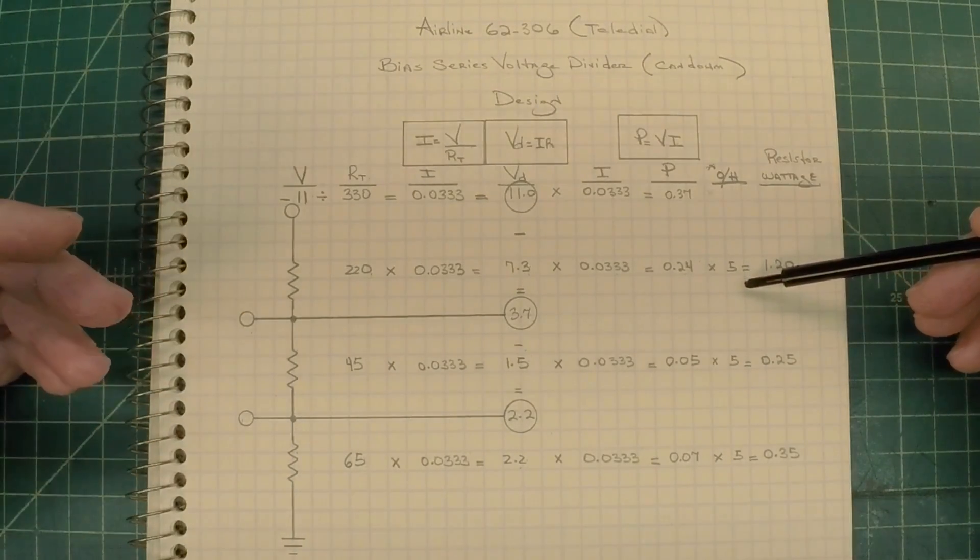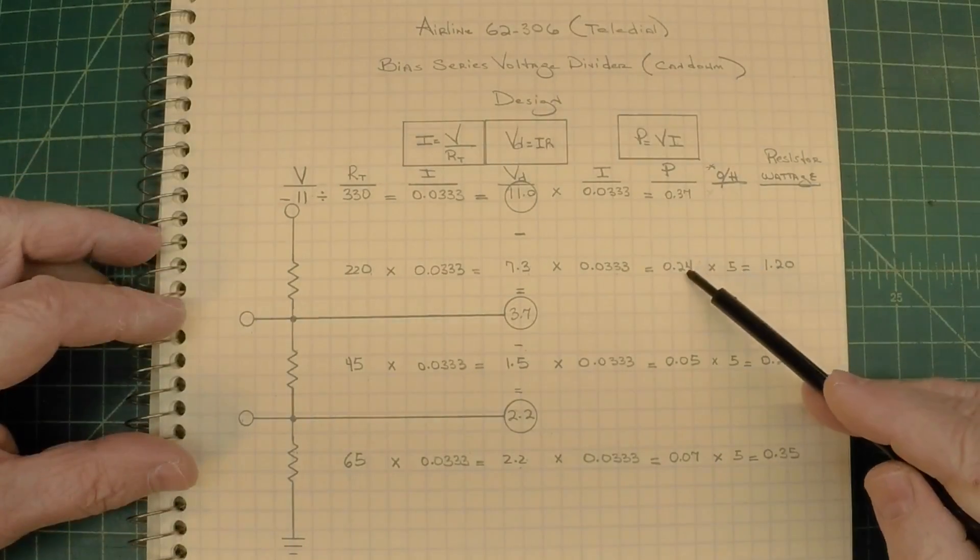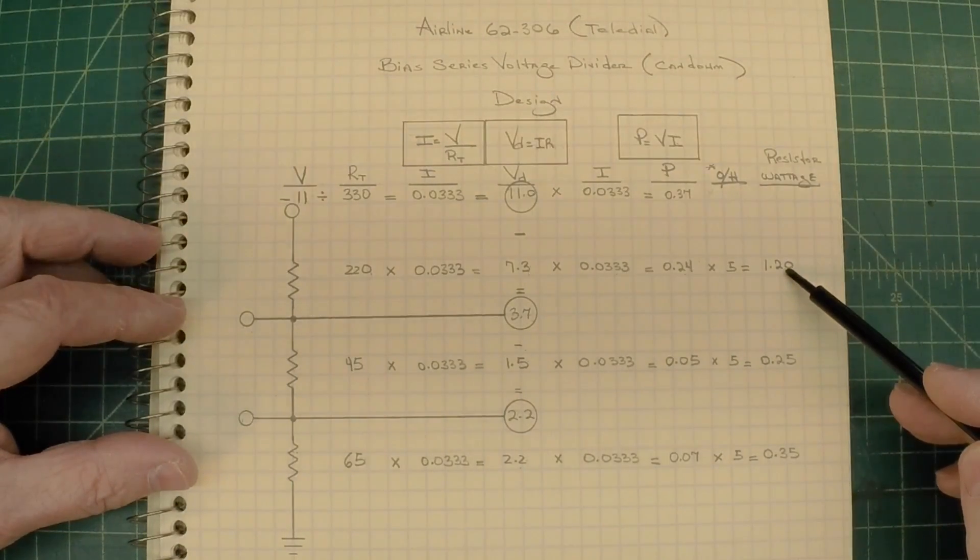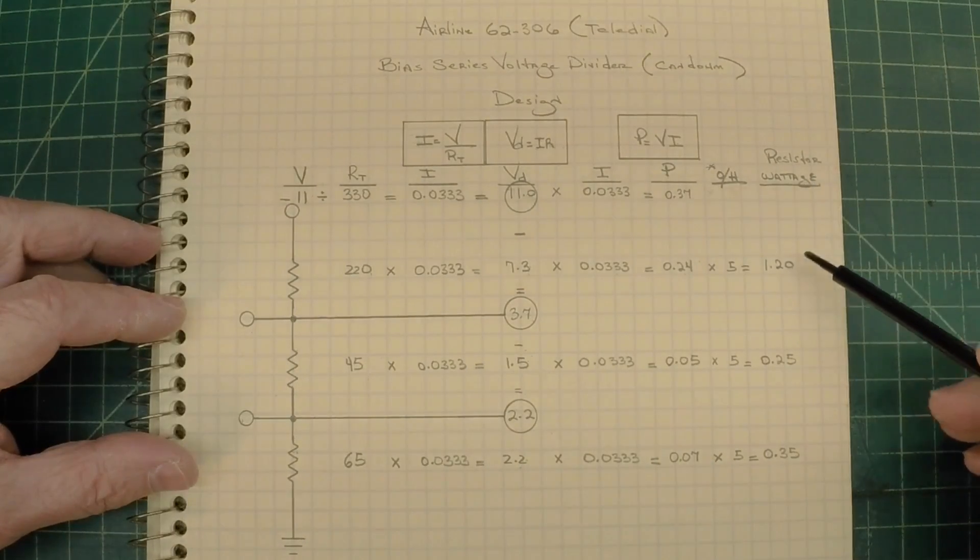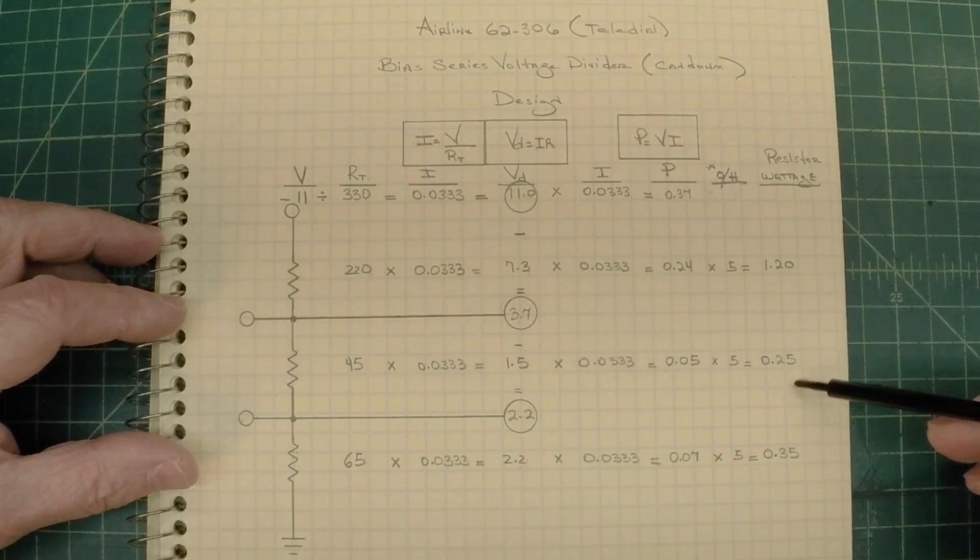Now you need an overhead factor because that's just the basic rating of the resistor itself. So I like using times 5 for terminal mounted resistors. So you can see I've done the math in this column. That would give me a resistor wattage requirement, just over a 1 watt, 1.2, 0.25, 0.35.